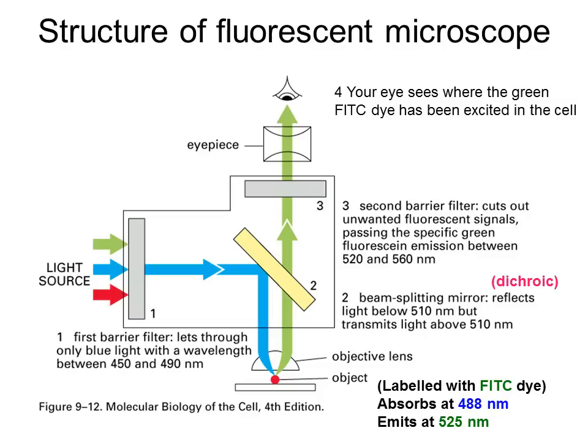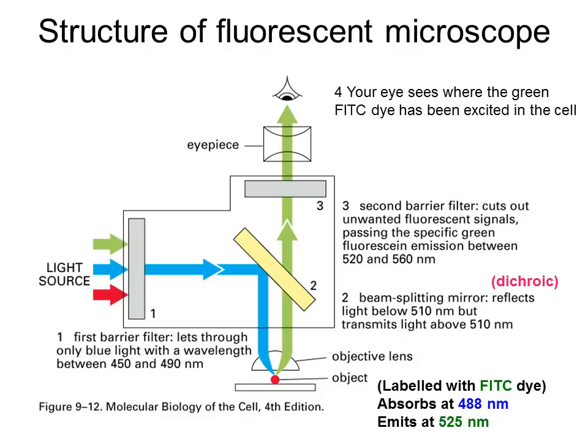The emitted fluorescent light at 525 nm passes back through the objective lens, which directs it to the dichroic mirror. Since this new light is of wavelengths greater than 510 nm, it passes through the mirror. That light then reaches a second barrier filter, which cuts out unwanted fluorescent signals and only allows light between 520 and 560 nm to pass. That passes through the eyepiece — providing a second level of magnification — and the green light eventually reaches the eye or the camera detector.